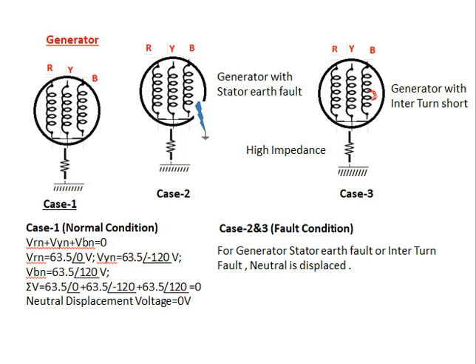In Case 2, a stator winding earth fault occurs, causing the terminal voltage to be reduced. In Case 3, a generator inter-turn fault occurs, and again the terminal voltage is reduced. Cases 2 and 3 are fault conditions — for a generator stator earth fault or inter-turn fault, the neutral is displaced.